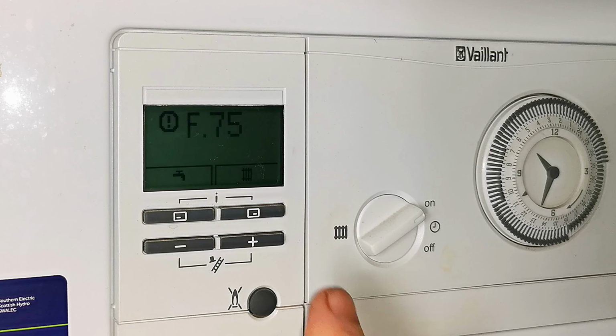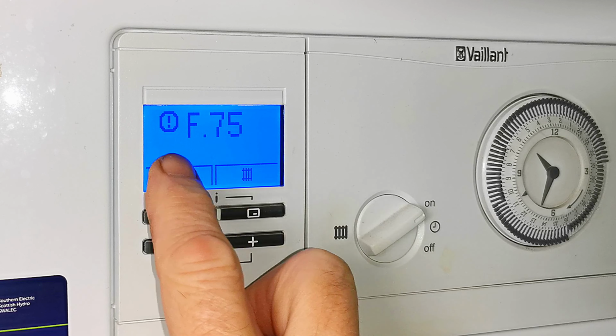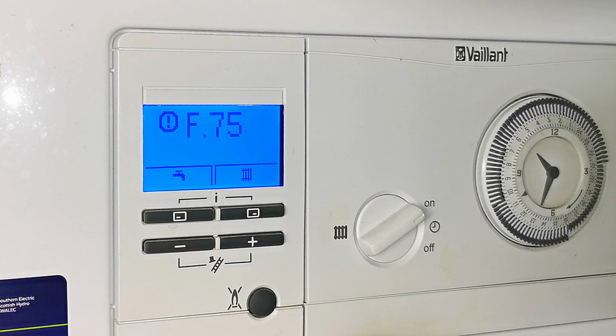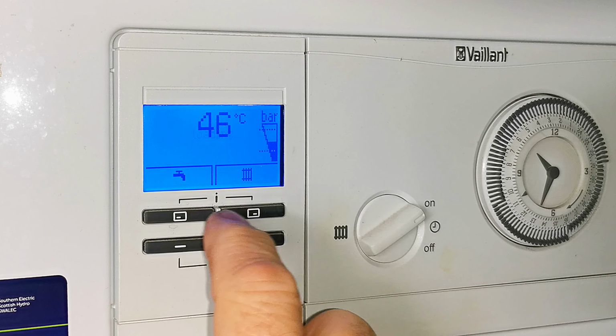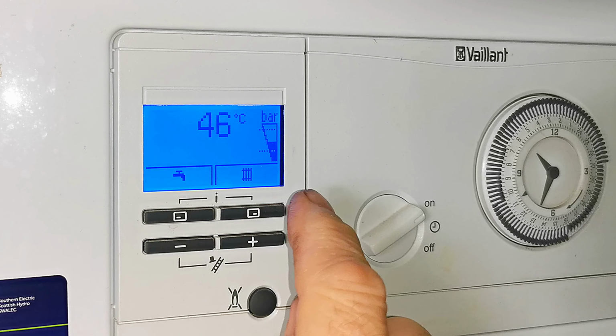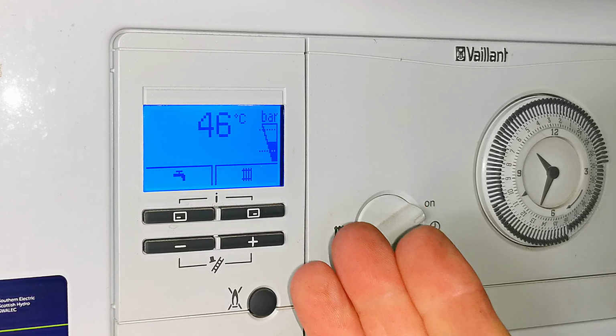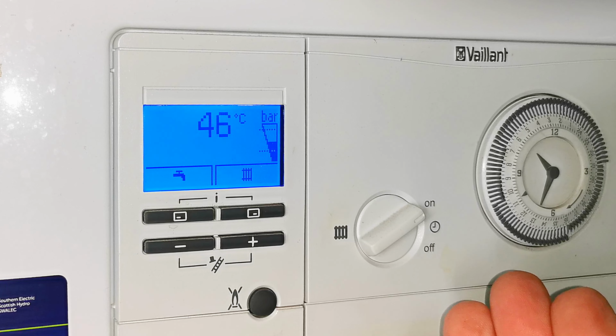So here's my Vaillant boiler, and we can see that it has F75 on the display. If I press the reset button, it's not very long before the boiler trips out again with the F75 fault. And that's because the pressure sensor inside the boiler is not seeing an increase in pressure because the pump is not running, which would increase the pressure.